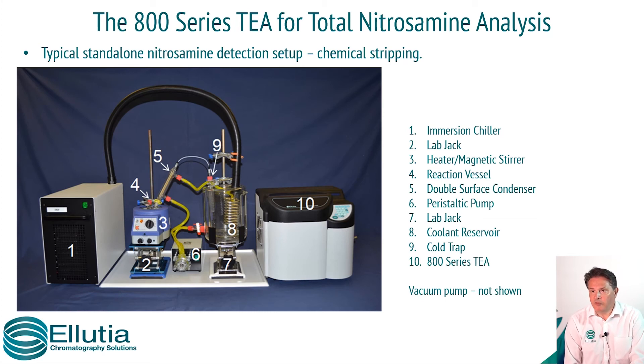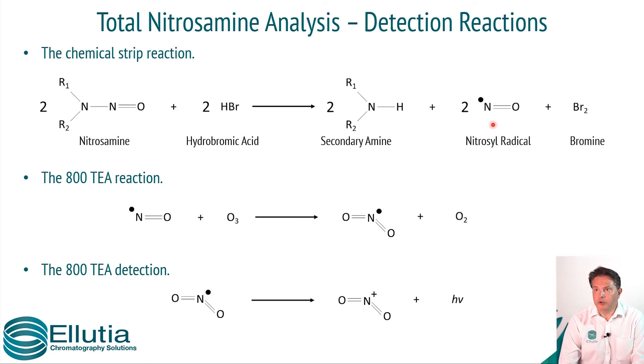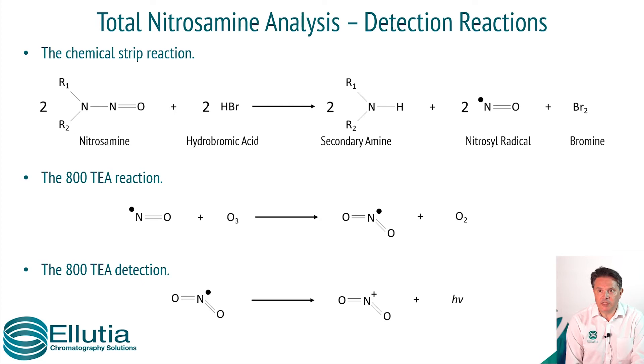This is a photograph of the glassware system that we supply. Similar to before, we use a chemical reaction. In this case, the hydrobromic acid is producing the secondary amine, releasing the nitrosyl radical and bromine. The nitrosyl radical enters the TEA, reacts with ozone to form the excited nitrogen dioxide molecule, which relaxes to release a photon of light, which is then detected.